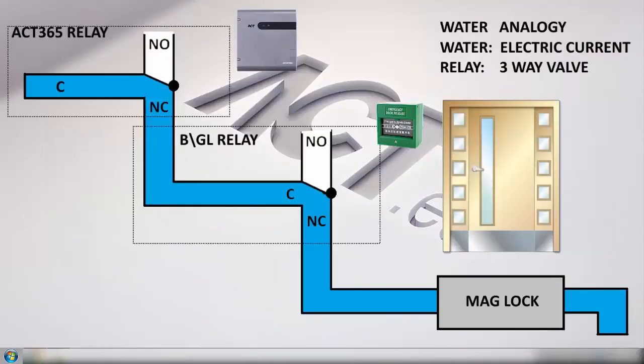In this instance the ACT365 relay is currently in its normally closed state so we can see the current or the water flowing in from common down into normally closed and then from normally closed it connects to common of the break glass. The break glass is in a normally closed position as well so the current or the water flows from common into normally closed.